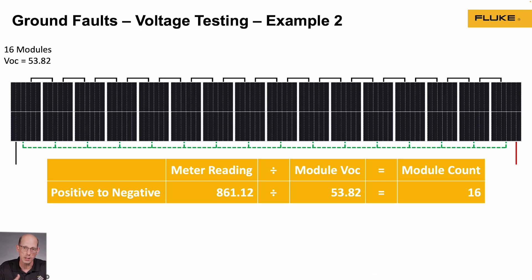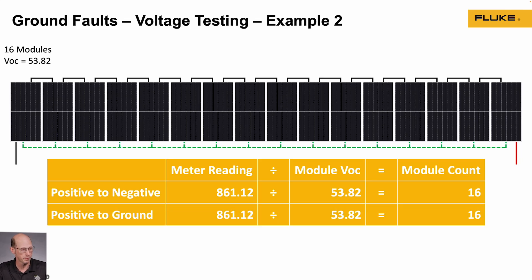In a second example, I measured from positive to negative and got the same result — 16 modules worth of voltage, which is what I expected. When I measured from positive to ground, I also got 861 volts where it should be zero, indicating 16 modules.